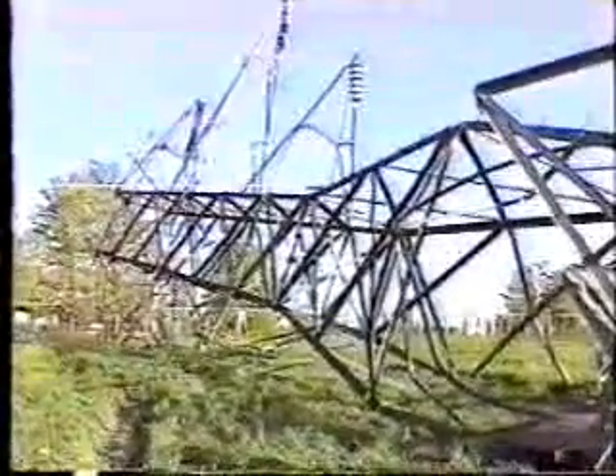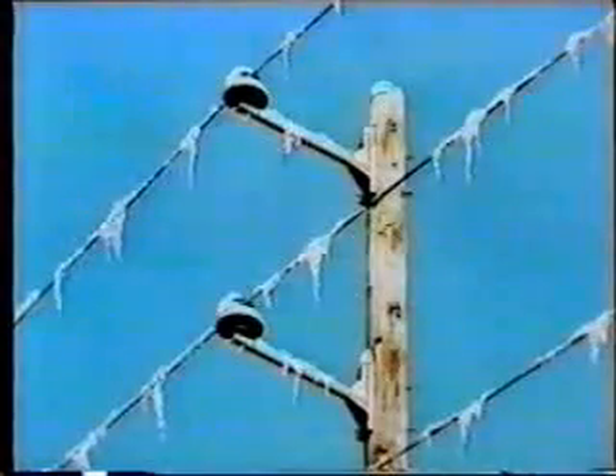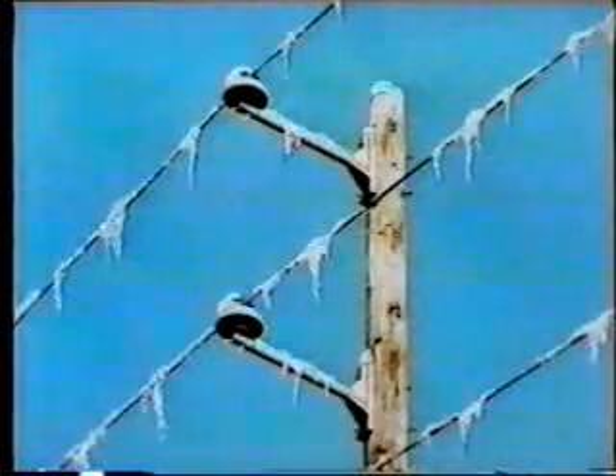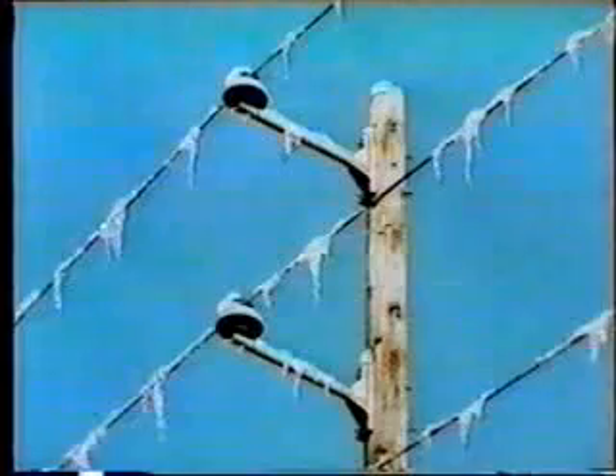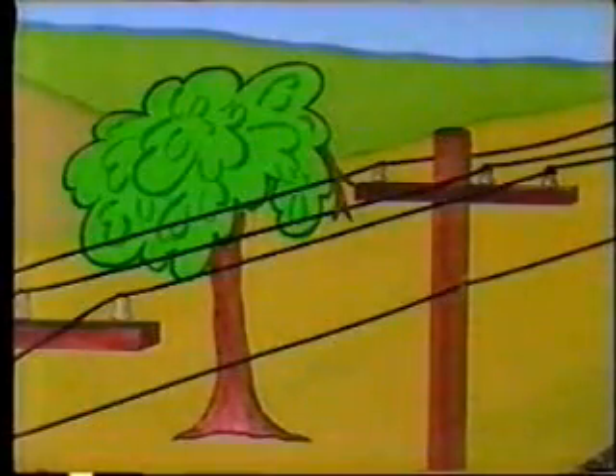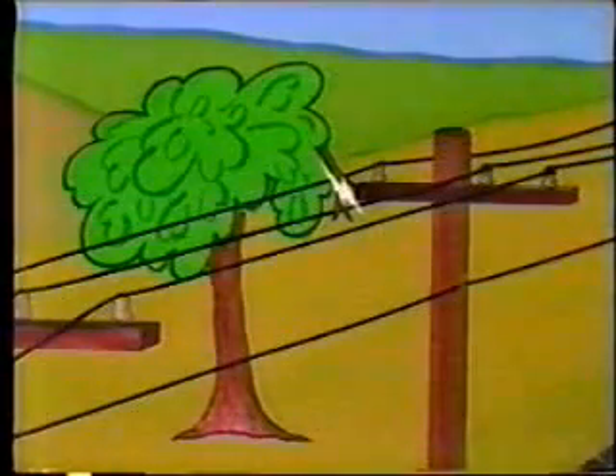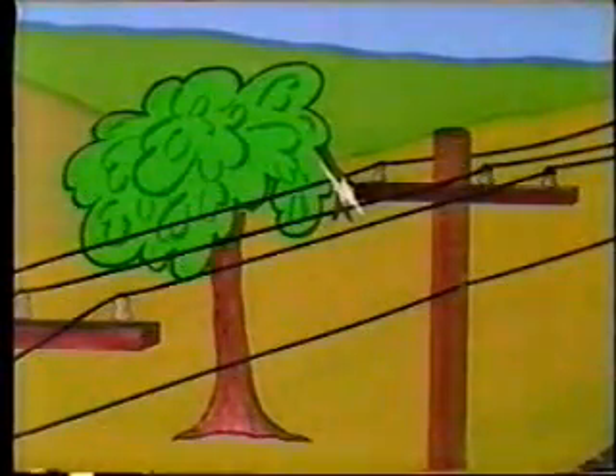So what could be the nature of a permanent fault on an overhead line? Well, one example is the collapse of the line as a result of hurricane or tornado damage to towers. Another weather-related possibility is the formation of heavy ice, which may stretch the conductors and perhaps cause eventual breakage. Another possibility could be, say, an aircraft or other object coming into contact with the conductors. All of these scenarios causing permanent faults are rare and unlikely occurrences. However, on distribution lines, a fairly common cause of a permanent fault is when the branches of a tree fall into contact with the conductors, causing a phase-to-phase or phase-to-ground fault.